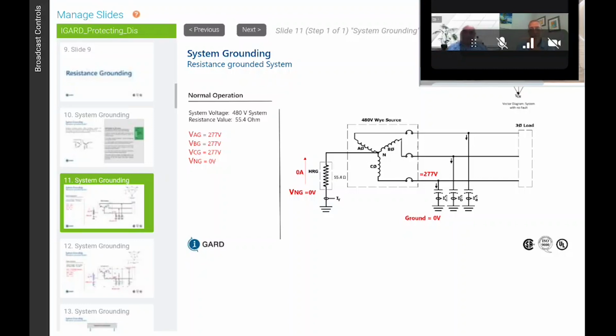Low voltage, again, with low voltage, it's going to be relatively small. The highest capacitive current, not leakage current, but capacitive current I've seen was on a system that had in excess of 50 generators at 13.8 kV, when we did the math and we calculated, it was over 500 amps. But it was like over 50 generators connected to one system with a lot of ties. But for low voltage, we're relatively going to have a small current. All right. Appreciate that answer.